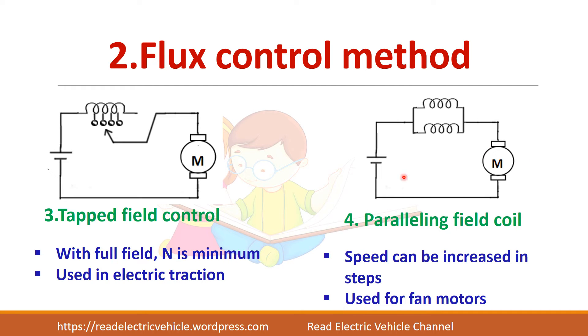This type of field control will be used in electric traction. Next we have paralleling field coils — that is, you can connect two or three coils in series and some of them in parallel. By using this, you are able to divide the current and the speed can be increased in steps. This type of paralleling field coils is used for fan motors.